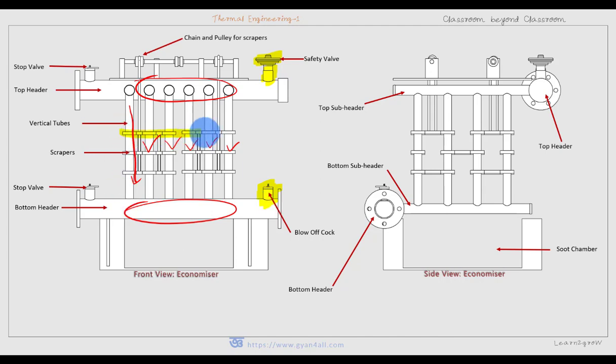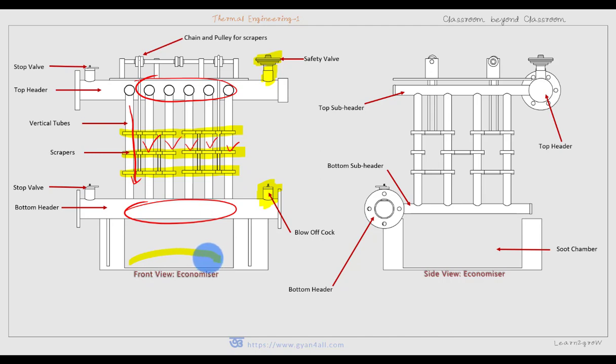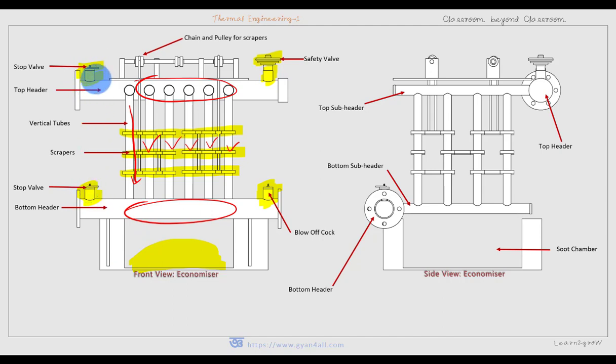The scrapers move up and down with the help of a chain and pulley arrangement, removing soot particles deposited on the vertical tubes. These soots are deposited at the bottom of the economizer in the soot chamber. There are two stop valves — one at the bottom header and one at the top header — provided to stop or allow water into and out of the economizer respectively.